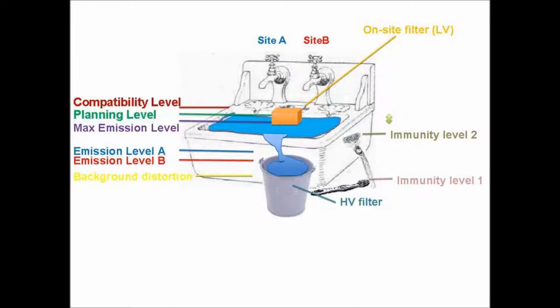So the first one is the compatibility level. That's the highest verified safe level. You've taken loads and loads of measurements over years and you know that there's no problem when you're at this level or below it. Once you go beyond it, you're starting to get on shaky ground, so you want to stay below that at all times. The planning level is what every engineer thinks of having, at least be below the planning level. Try and maintain some sort of safety margin.